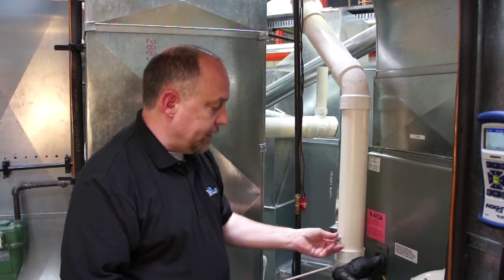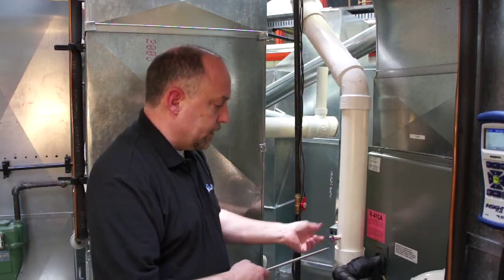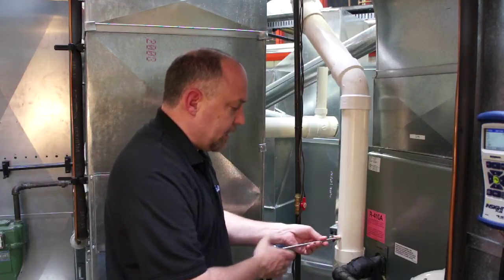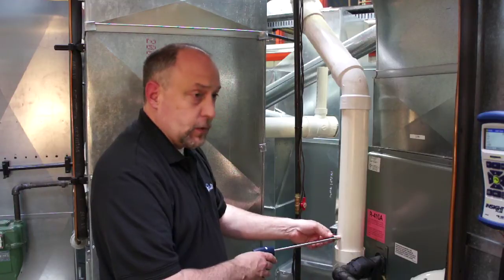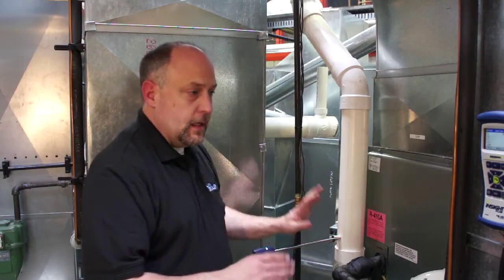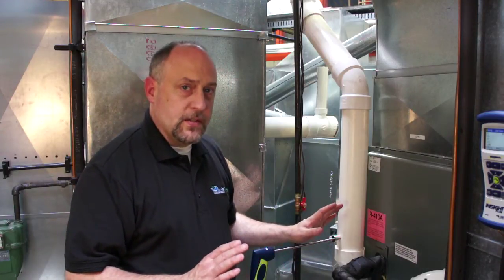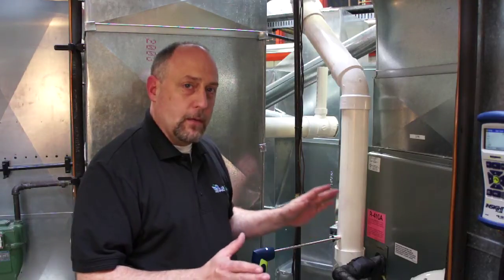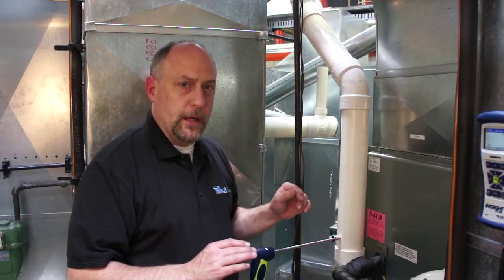And these are all threaded, so we're going to go ahead and screw that in there and lock it in place. I usually just take it to the back of the flue pipe, pull it out towards the center, and just lock that in. And so now we can start doing our combustion test. I'm going to go ahead and get the furnace fired up, and we'll show you what we can see on the display.